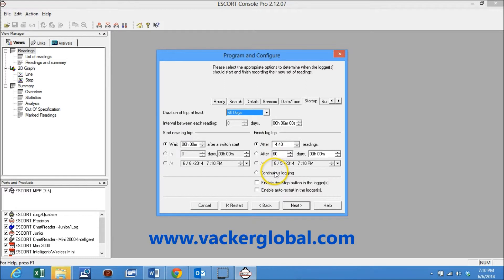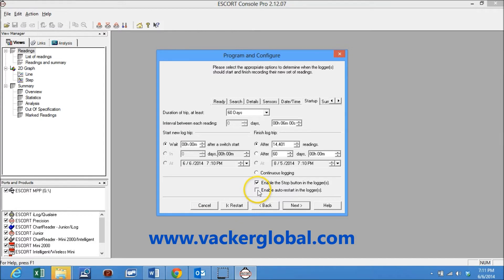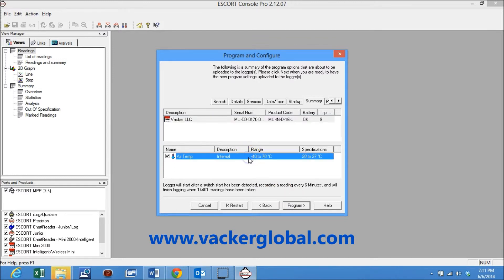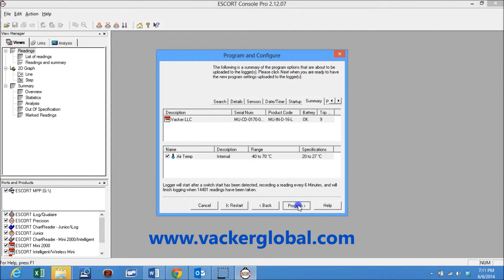The stop button can be disabled or enabled. Enabling auto restart means if an alarm is not generated during the recording or if the alarms are not programmed, the logger can be started and stopped using the respective buttons. However, if an alarm is generated the logger needs to be downloaded and rearmed.